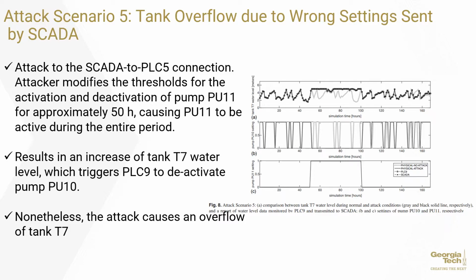Scenario number 5 is called tank overflow due to wrong settings sent by SCADA. The attacker on the SCADA to PLC connection this time modifies the threshold for the activation and deactivation of pump 11 for approximately 50 hours. That causes pump 11 to be active during the entire period. So obviously from attack scenario number 5, we expect the third indicator, the efficiency of the pumps, to be pretty high. And these scenarios result in an increase of tank 7 water level, which triggers PLC9 to deactivate pump 10.